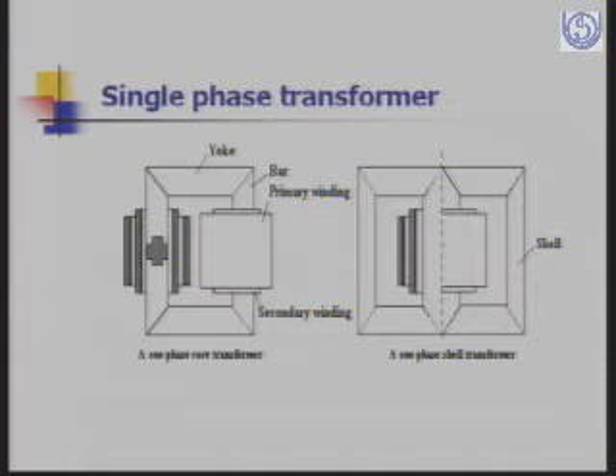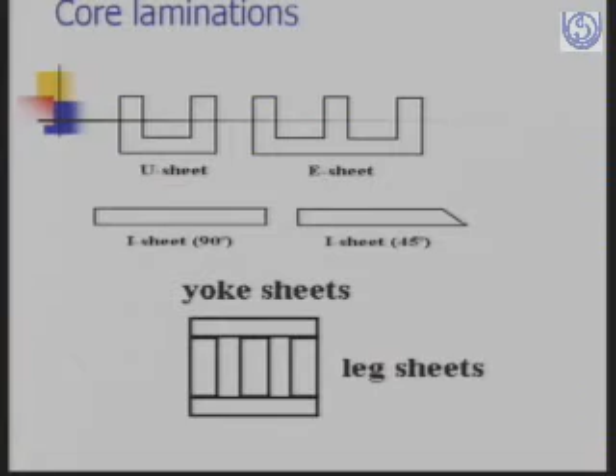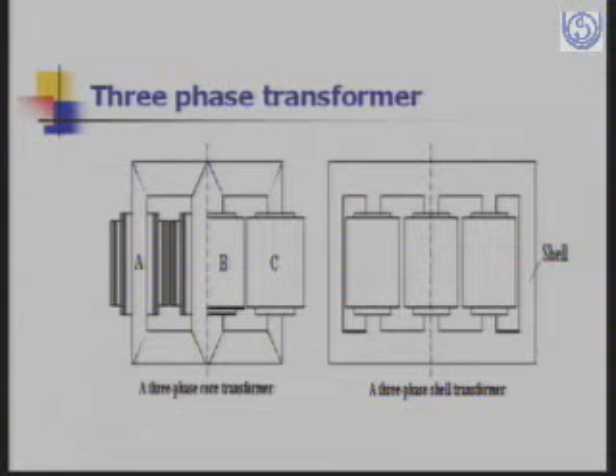The laminations of these cores, the magnetic material, are made of U sheet, E sheet, I sheet of 90 degree, I sheet of 45 degree, and the yoke sheets and leg sheets are attached as shown in the slide. So these laminations usually make up the core, and they are made of CRGO steel, or we now have a new material which is known as amorphous material. The amorphous material is also a type of steel, but it does not have a crystalline structure; the molecules in the amorphous material are randomly placed, and the losses in the amorphous core material are much less as compared to the CRGO steel. That is why in the distribution systems we are now using transformers made of amorphous core.